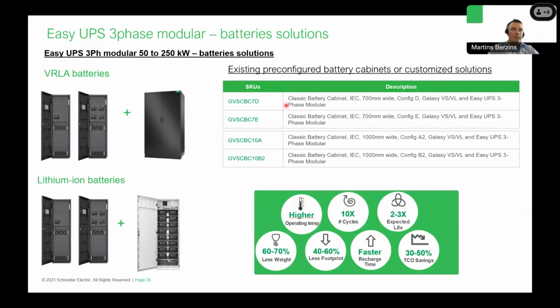Regarding the batteries, as said earlier, the UPS can accept VRLA, or valve-regulated lead-acid, batteries. It can be either implemented in battery cabinets, or if necessary, we can also provide the batteries on an open rack. And the three-phase modular can also accept a lithium-ion battery solution. So what are some benefits that lithium-ion has versus lead-acid? Lithium-ion can operate at higher operating temperatures. As you know, for lead-acid batteries, the optimum operating temperature is 20 to 25 degrees, and if the temperature increases to 30 or even more degrees, the lifetime of the batteries decreases drastically. For lithium-ion, this is not much of a concern. They will derate, but not to such a high level.